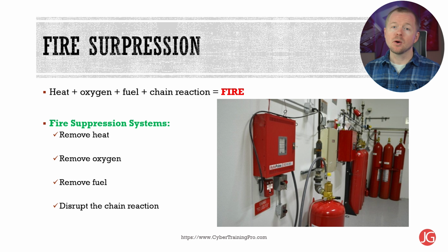They can remove heat with either chemical agents or water. However, with electrical fires, we would never want to use water. They can remove oxygen with either carbon dioxide, CO2, or similar gases. They can remove fuel, meaning that there's nothing left to burn, but this isn't a typical strategy. And they can disrupt the chain reaction by using specific chemicals and thereby stopping the fire.